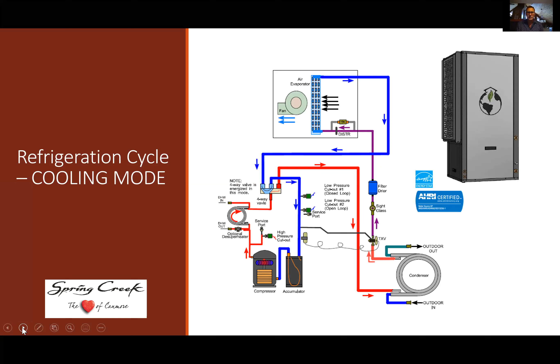And the nice thing about this in big buildings or different facilities is that you can run heating and cooling simultaneously. Some of my large buildings will be calling for cooling loads on one side of the building because it faces south, while the north side of the building is calling for heating. By running our heat pump, we can feed both tanks, to cool our cold water tank or heat up our hot water tank, depending on the requirement. Any excess heat or cold can be sent to the field through a 3-way valve. So that's another beauty of GeoExchange, that we're able to do both at the same time.